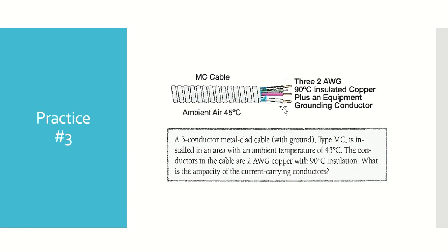Look at number 6. 6 is grounding or bonding conductor. It says a grounding or bonding conductor shall not be counted when applying the provisions. So in this scenario, we do not have to count it. So going back to my original statement, I was wrong when we counted for 4.